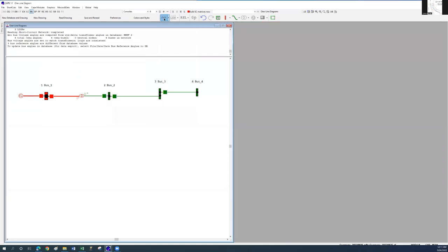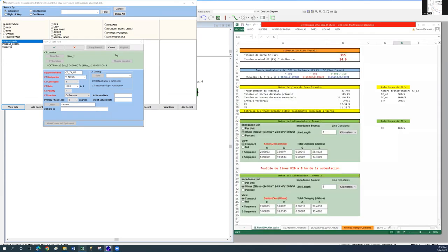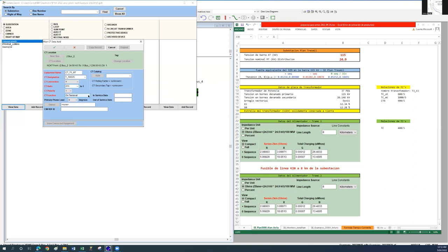Choose and drag the CT icon onto the transformer logical breaker. Name it and specify its designation as shown. In the CT ratio field, insert 200, which is equal to the ratio of 1000 to 5. On the CT terminal field, select on terminal.